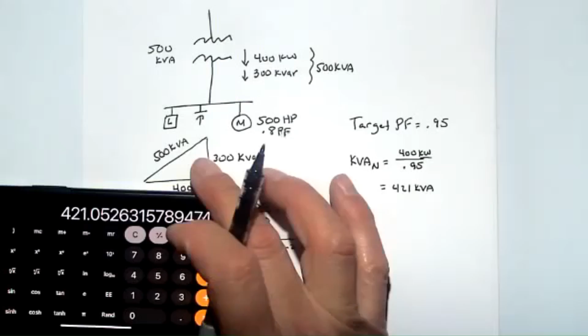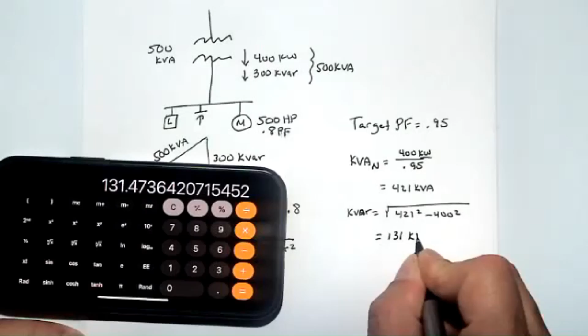Well, first I have to figure out how many kVAR are left if I do that. I know my new kVA is 421, so my kVAR would then be the square root of 421 squared minus 400 squared, which is my kilowatts. So 421 squared minus 400 squared, take the square root of that, and I'm left with 131 kVAR. Now what's important to know about that is that's what's going to be flowing up through here, 131, if we had a 0.95 power factor. I still have 400 kilowatts flowing through there.